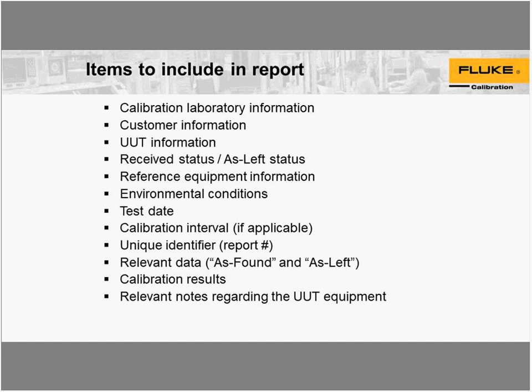Reference equipment information. So you'll see in this example report that I have for you, it does have the reference equipment listed. You should have environmental conditions listed on your cert. Depending on what your lab criteria are, it needs to be within spec. I'll need a test date. You include a calibration interval if it's applicable. There are a lot of people out there that when they send their items in for calibration, they request a date of not determined. So we come out, there is no interval or expiration date, and they manage that internally.